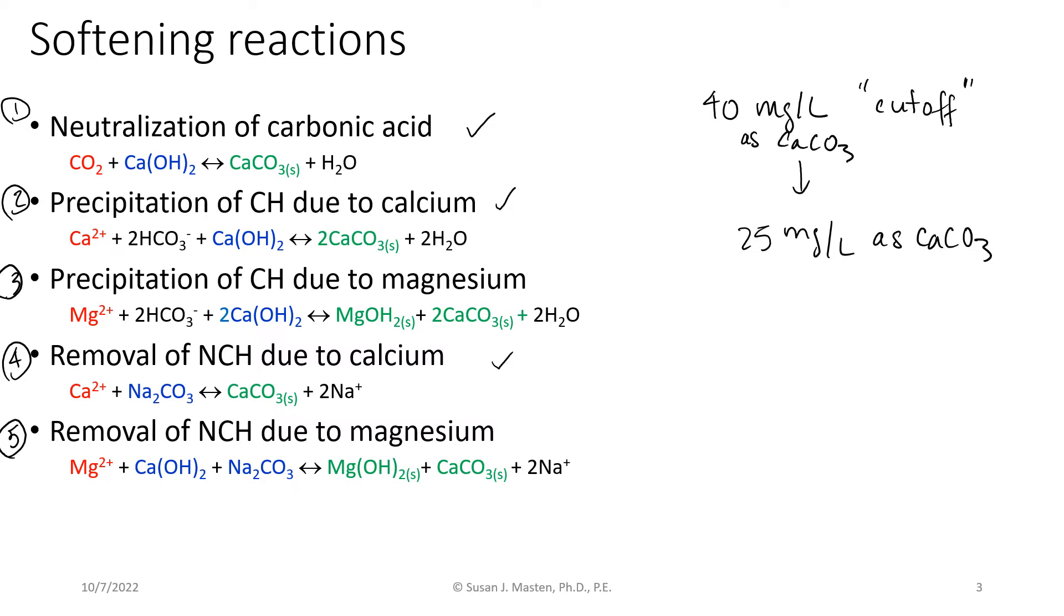Remember, in terms of the pH, if we're removing magnesium, we need the pH to be about 11.3. But if we're only removing calcium, we can operate at a pH of about 10.3. So that helps to govern which of these species we actually remove.